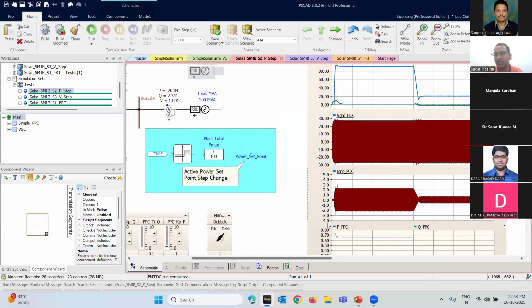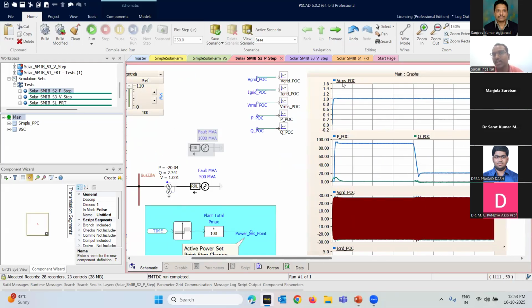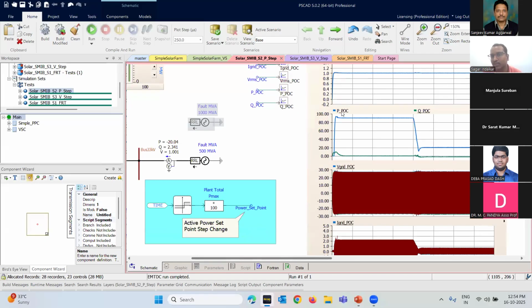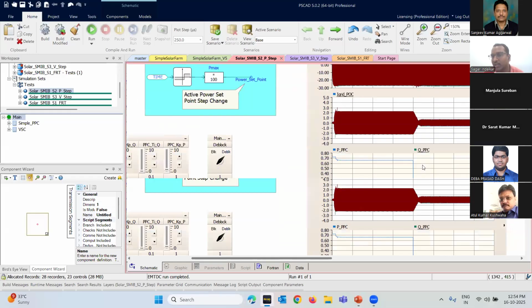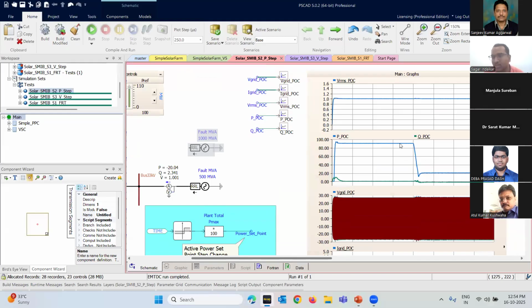On the right, if I just move up, you see this is my VRMS V1, the RMS voltage, which you see is more or less stable, constant. At the bottom, what you have is your PPOC. PPOC is the active power measured at POI. The one in blue is your active power measured at POI. The one in green is your reactive power measured at POI. So if you remember, for the first 10 seconds my active power set point was 90 megawatt or 0.9 per unit, which changed to 0.2 per unit at t equal to 10 seconds. So that set point changed, and so my active power at POI changed from 90 to 20.